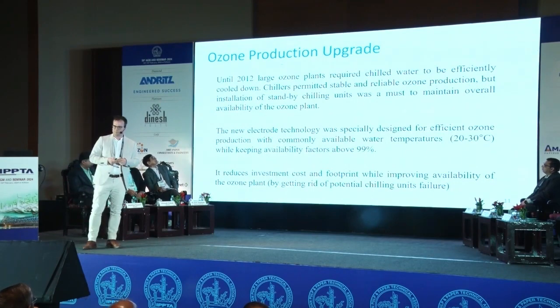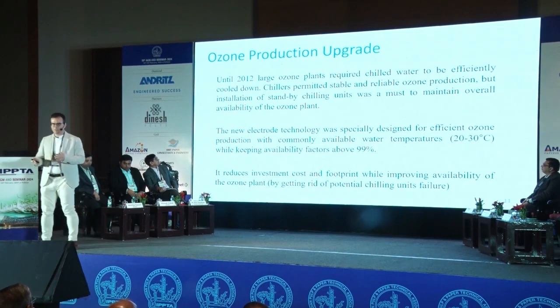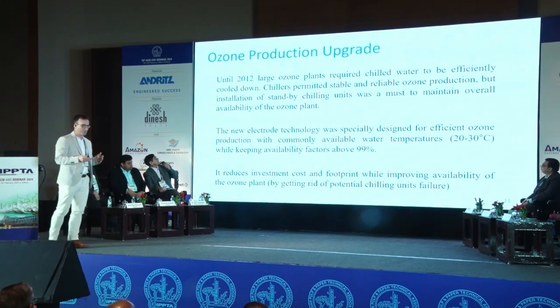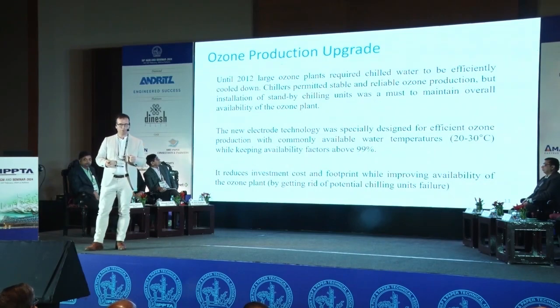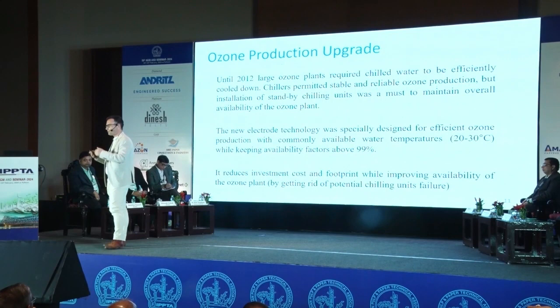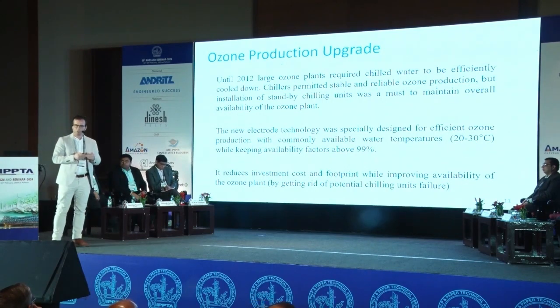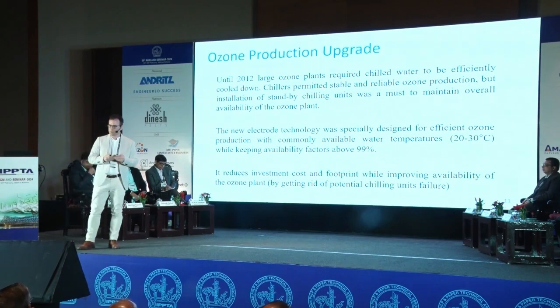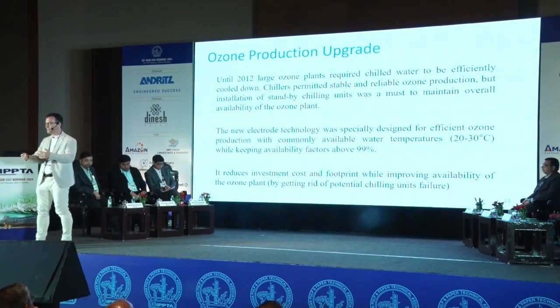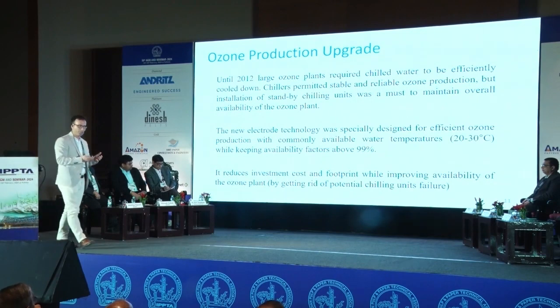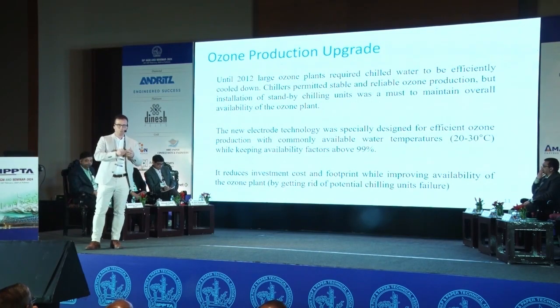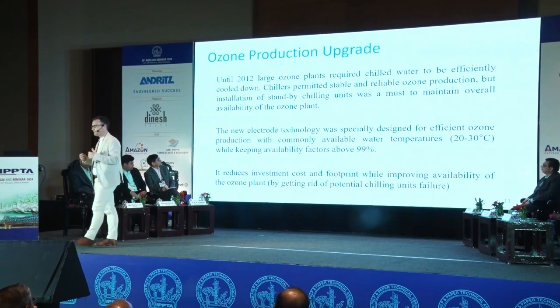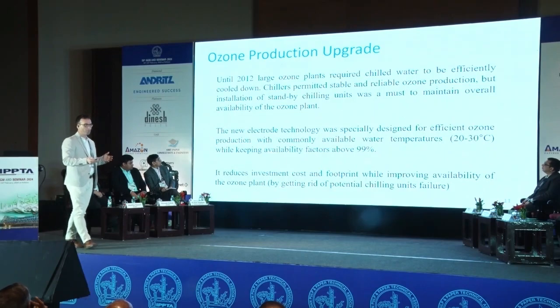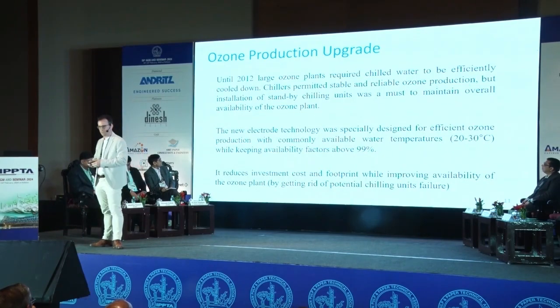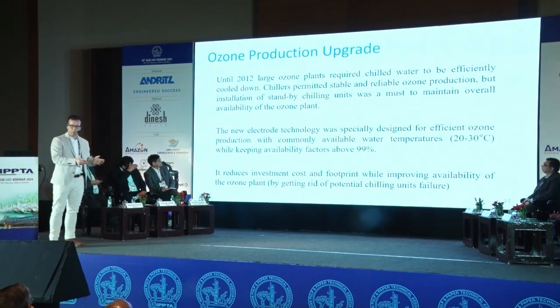I said it was an older technology because in 2012, ozone production technology improved significantly, because in the past, like for chlorine dioxide, there was a need for chilled water to efficiently cool down the ozone systems. Today we can operate with cooling water temperatures up to 30 degrees, meaning we don't need to invest in any chiller and to operate any chiller. It makes availability of the ozone plant even better, because in fact failures were coming from chilling units, not much from the ozone system itself. And it reduces, of course, OPEX and CAPEX of the plant.